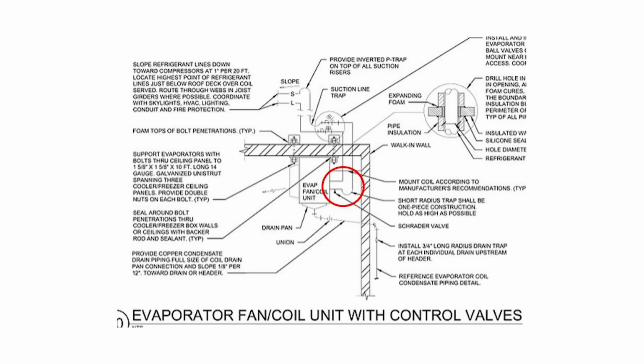It doesn't have to be at the evaporator. It can be in other places too. But traditionally, there is one at the evaporator, maybe more farther down. But I've got to have a trap at the bottom of that riser. That's where it needs to be. And what that's going to do is it's going to prevent, in low velocity or when that circuit shuts off or defrost or cycles off on temperature, that riser is going to be full of oil. The oil will fall. And I want it to fall into my trap instead of falling into my evaporator.